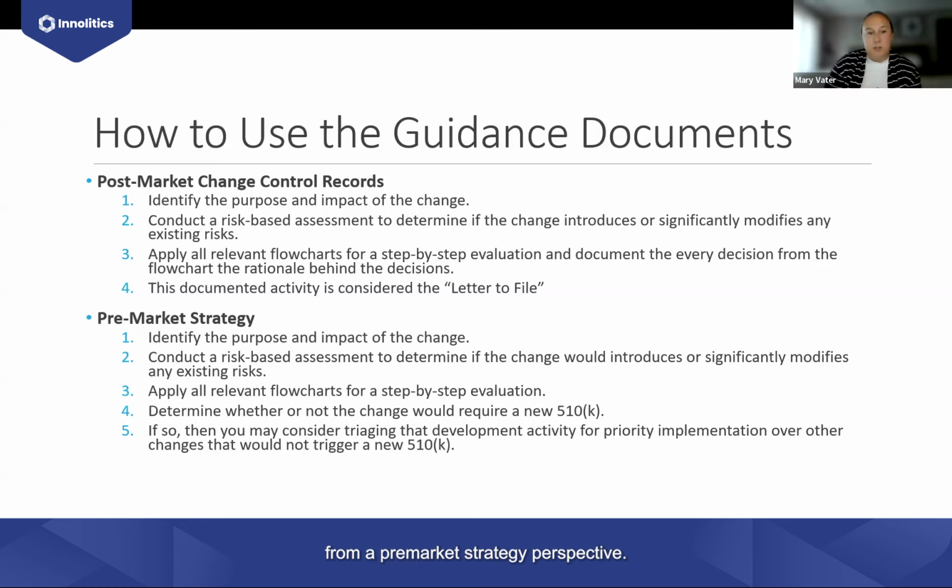From a pre-market strategy perspective, of course, this is not something that is like an active change to a marketed device. So the FDA is not as concerned with your documentation proactively, but it's still a great exercise to go through the processes that you would post-market by identifying the purpose of the change, conducting the same risk assessment, because all of these things are necessary in order to really ensure and to really document that you've adequately evaluated the changes, applying the flowcharts, doing the step-by-step evaluation, and making a proactive determination as to whether or not the change would in the future require a new 510K.